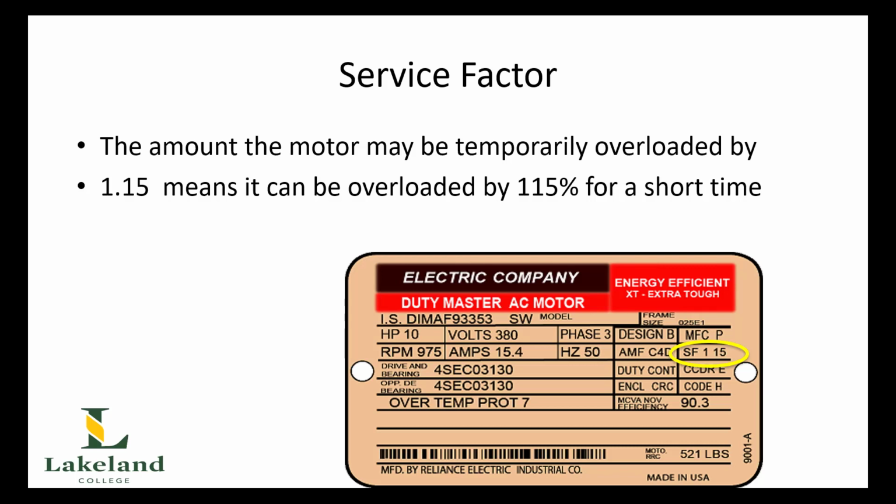The next one is the service factor. Typical service factors on motor nameplates are 115, which means that the motor can be overloaded for short periods of time up to 115%. Now, what does overloaded mean? It means basically increasing the load by more than 15% of its rating. What's the load? The value at which it can drive. How can you rate the load? You can rate it in load current, or you could rate it in torque. Either way, exceed that by 15%. That's permissible, but only for short periods of time. Ideally, we should not be exceeding these ratings because then the motor will overheat.